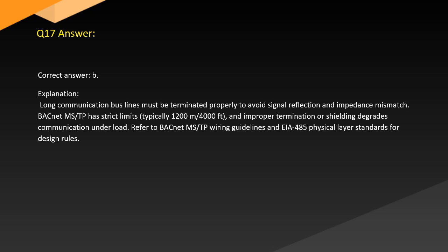Answer. Correct answer: B. Explanation. Long communication bus lines must be terminated properly to avoid signal reflection and impedance mismatch. BACnet MS/TP has strict limits, typically 1,200 meters, or 4,000 feet, and improper termination or shielding degrades communication under load. Refer to BACnet MS/TP wiring guidelines and RS-485 physical layer standards for design rules.